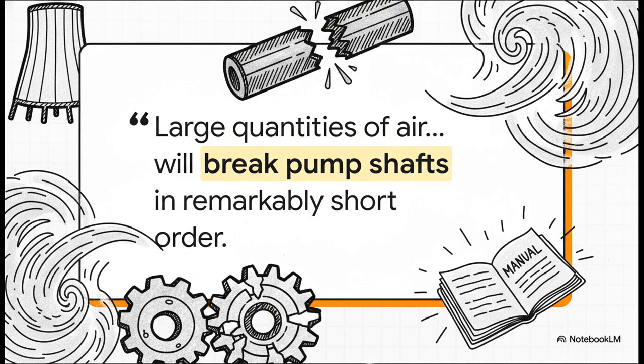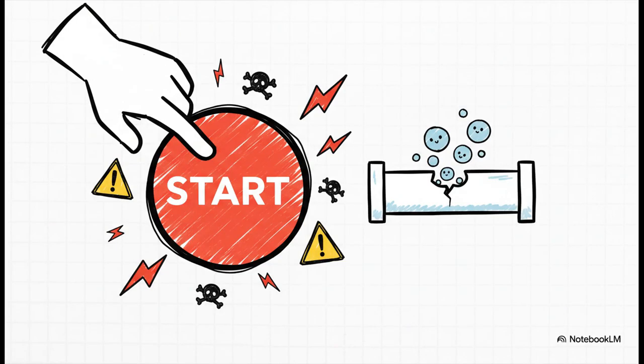And the consequences? They are incredibly severe. This is not a minor problem. The source manual is crystal clear about this. It says large quantities of air will break pump shafts in remarkably short order. We're not talking about long-term wear and tear here. We're talking about shearing a solid steel shaft clean off, and fast. So how does this killer even get inside the system? Well, believe it or not, one of the most common ways is through a totally avoidable but disastrous mistake that happens right when the system starts up.